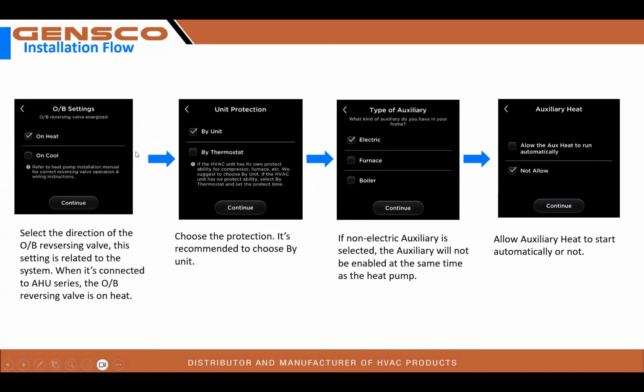Our OB settings: our reversing valve is energized in heating. Unit protection. What type of auxiliary heat are we using? Are we using electric heat? No electric heat? Are we dual fuel? Are we running a boiler? You pick what the auxiliary heat is.